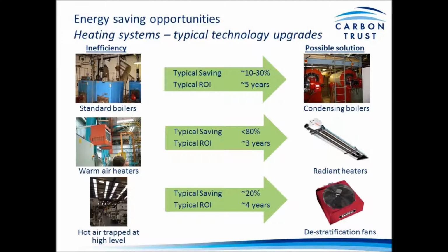Something we often see in warehouse or manufacturing type spaces where you have high ceilings is that warm air rises and heat is lost through the roof, which is trapped at high level. Destratification fans can be an effective way to blow warm air back down to ground level where it is needed. That warm air is picked up by your local thermostats, and it can save you up to 20% on your energy bills. The typical return on investment we see for these types of systems is around the 4-year mark.